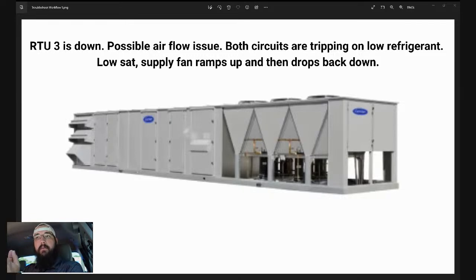I feel like next time we go back here, I'm not going to commit to the TXV and the low charge diagnosis yet, because before he locked it off, as it was running, if that static pressure was fluctuating as much as I understood it was in talking to him, then that's going to cause a heavy fluctuation on our superheat and our TXV. We have to keep in mind that in the sequence of things, your evaporator coil is at the mercy of the airstream. Whatever the airstream does, whatever the fan does, it is at the pure mercy of what it decides. So we have to think about that.